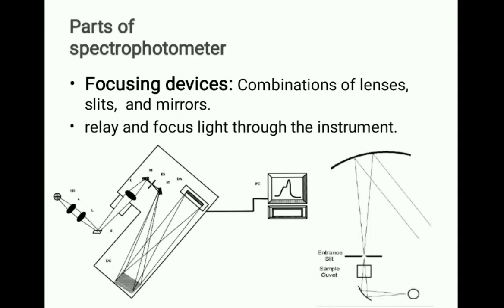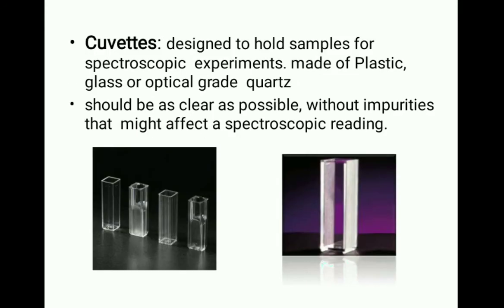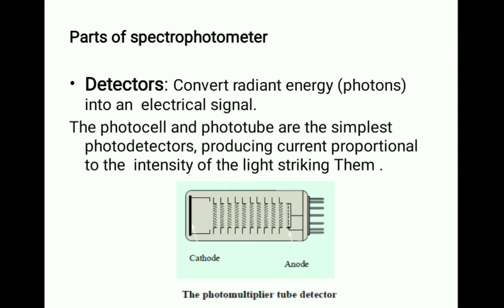Next we have a focusing device — the combination of lens, slit, and mirror — to relay and focus light through the instrument. Then we have a cuvette designed to hold sample for spectroscopic examination, made up of plastic, glass, or optical grade quartz. It should be as clean as possible without impurities that might affect a spectrophotometric reading. Next we have our detectors that convert radiation — photons — into electrical signals. The photocell and the phototube are the simplest photodetectors, producing currents proportional to the intensity of the light striking them.